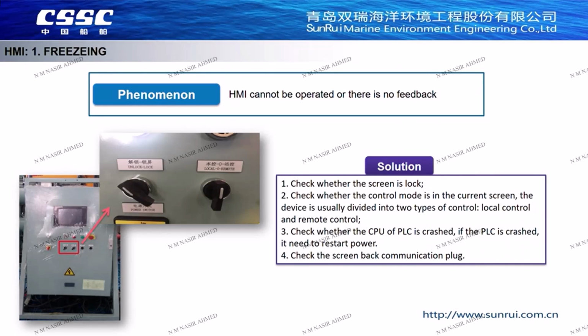The last introduction is the control screen being frozen and unable to be operated. First, make sure the screen is unblocked from the operation and the operating permission is given to the in-use screen. Secondly, check whether the PLC has crashed, which may be confirmed by clicking the screen with no response, and the PLC CPU module's error LED lights. It can only be reset by rebooting the system to restore from the crash.